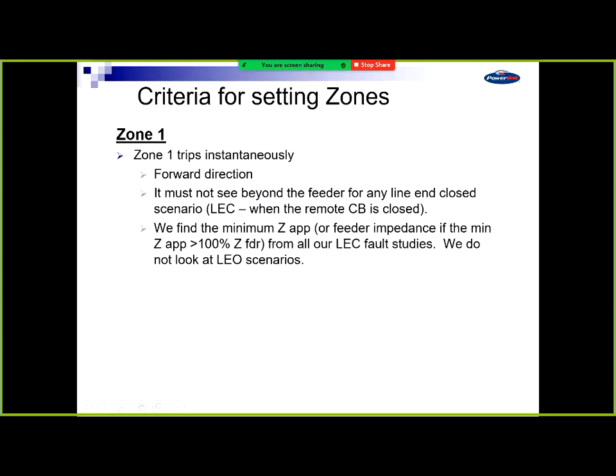So your zone 1 trips instantaneously, it's forward looking. When we set them, that line end closed. That's all you need to worry about. If your remote end breaker is open, circuit breaker is opened, you're not going to trip spuriously. The fault can't be beyond, you can't see a fault beyond that because you're not going to send current through. So you're not worried about a line end open scenario, which is what we call an LEO. So you can trip instantaneously because the fault can't be beyond the feeder. So we only look at line end closed scenarios for our zone 1.